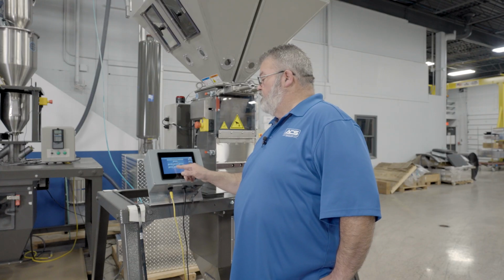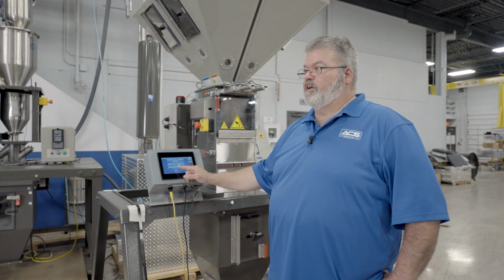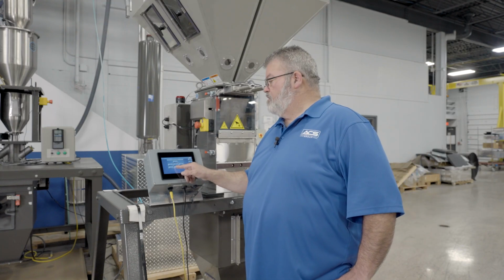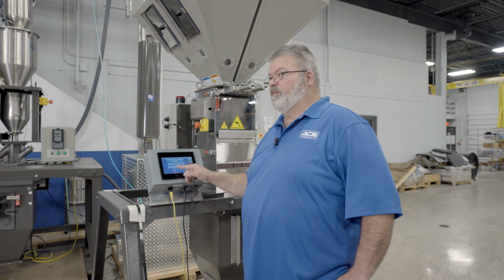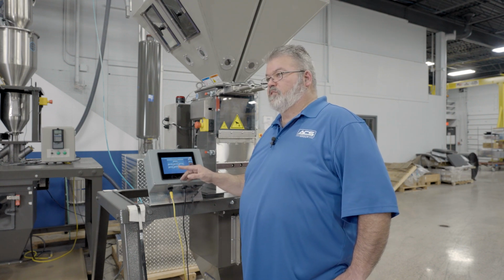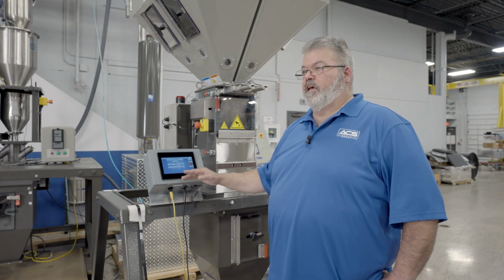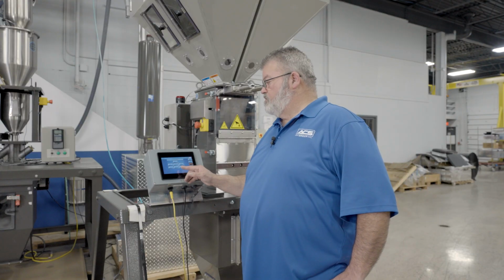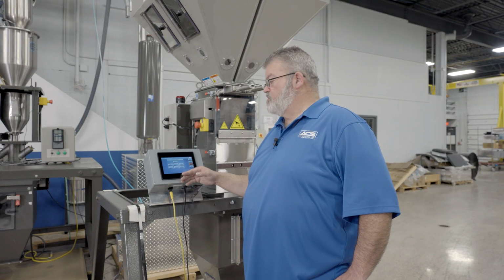And right now we always send these out default weigh every batch. If for some reason your blender won't keep up with your process, you can change this to weigh every other batch all the way out to every 5th batch. What that'll do is the non-weighed batches will meter off of time, and all the gates open at the same time. So it will speed up the blender, and you'll get a higher process rate.